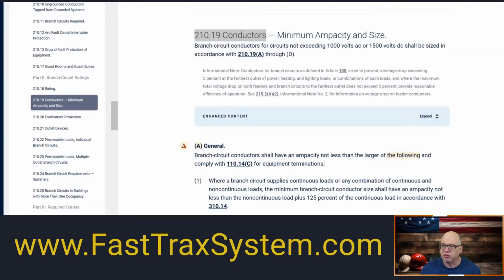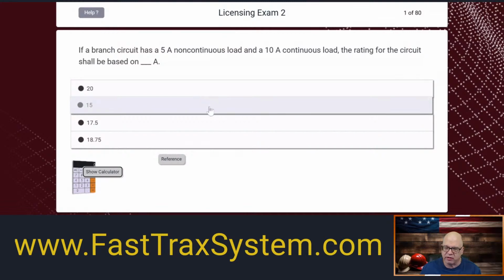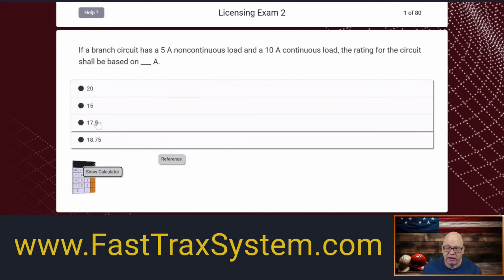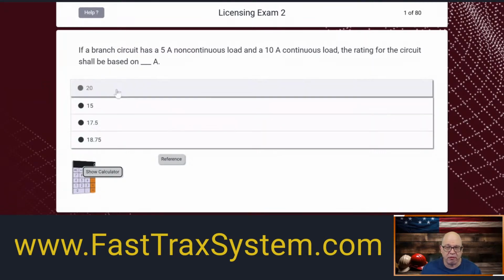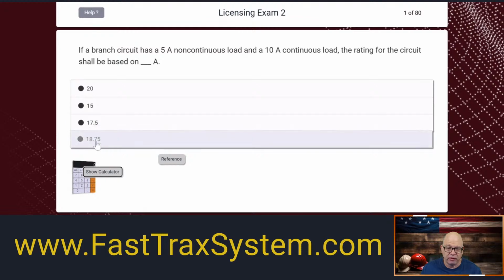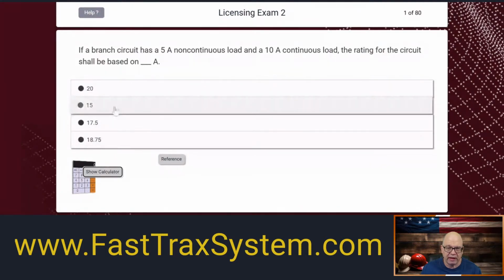Okay. All right. Real quick, I wanted to show you a process of elimination. One of the things that I teach students in question review is to get rid of the obvious. First things first, you know the answer is not going to be 15, right? Because if 5 is continuous, 5 is non-continuous and 10 is continuous, you automatically, through your training, know that we have to do something different for the continuous load than we do for the non-continuous load, right? So you can immediately throw out the 15. So you have now increased your odds to 33.33 percent of getting it right, because it's either 20, 17.5, or 18.75. Okay, we already know that. So get rid of the 15.